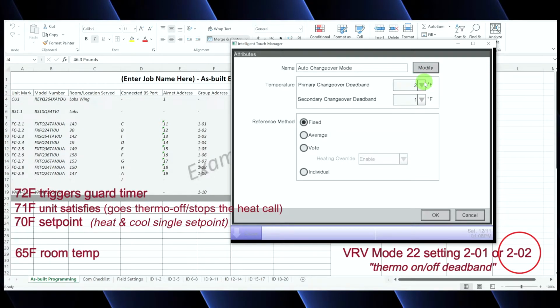And that's because you're going to have a 1 degree overshoot every single time already because of the thermo on-off deadband. Your unit is in heat, heats to 70, satisfies at 71. If you set this to 1, then as soon as the unit satisfies, it's going to switch to the opposite mode. It's going to start cooling down to 70. It's going to satisfy at 69, and it's going to immediately switch back to heat. Oh my gosh, you're going to have comfort issues, you're going to have complaints, and potentially performance issues as well. So this deadband needs to be at least 1 degree past the thermo on-off deadband.